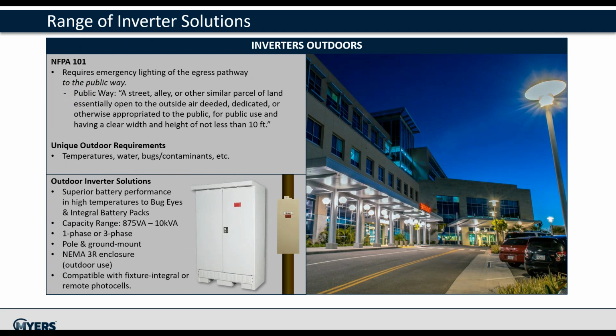One of the points that was touched on earlier was NFPA 101, defining the path of egress, which requires emergency lighting to illuminate to the public way. The definition of the public way is a street or alley open to the outside air, deeded, dedicated, or otherwise appropriated to the public for public use, having a clear width and height of not less than 10 feet. This is a long-winded statement that says the illumination must extend away from the building to a safe area.